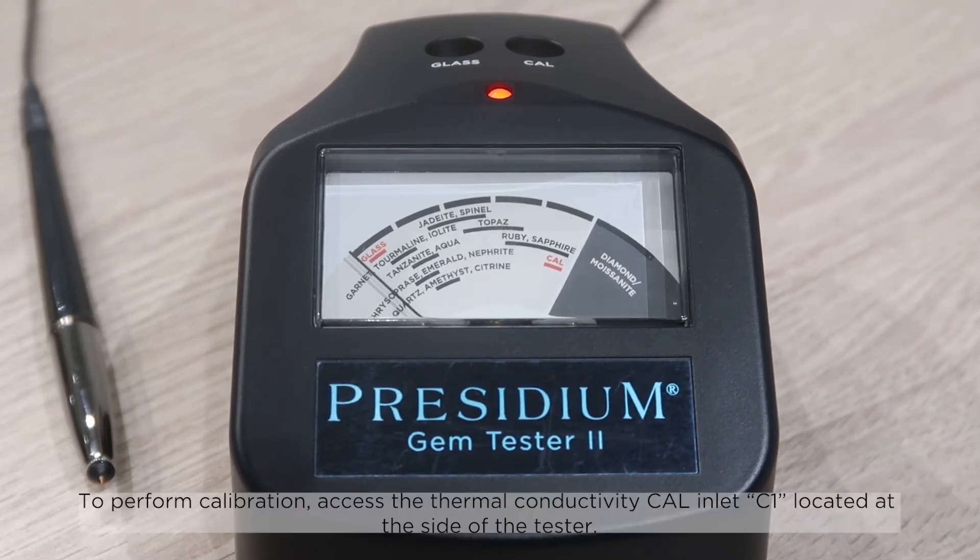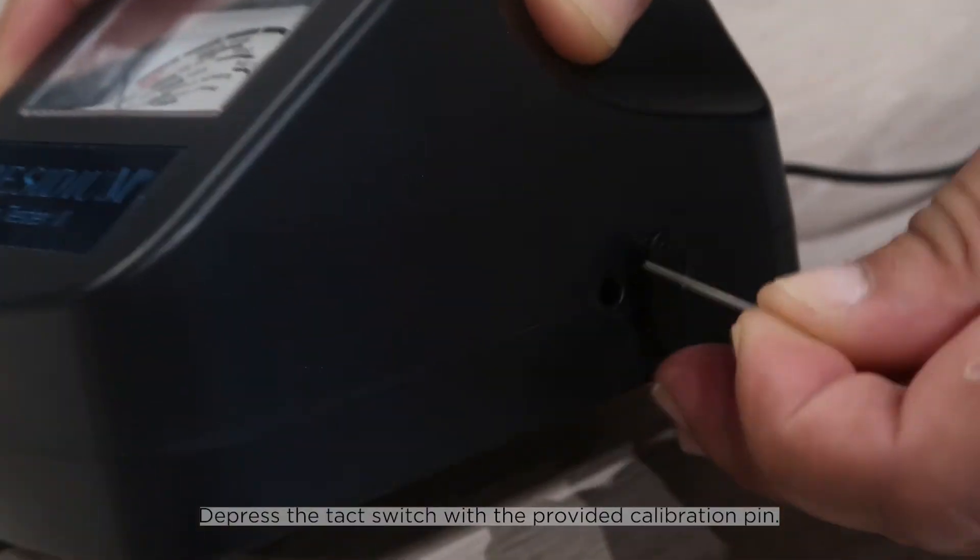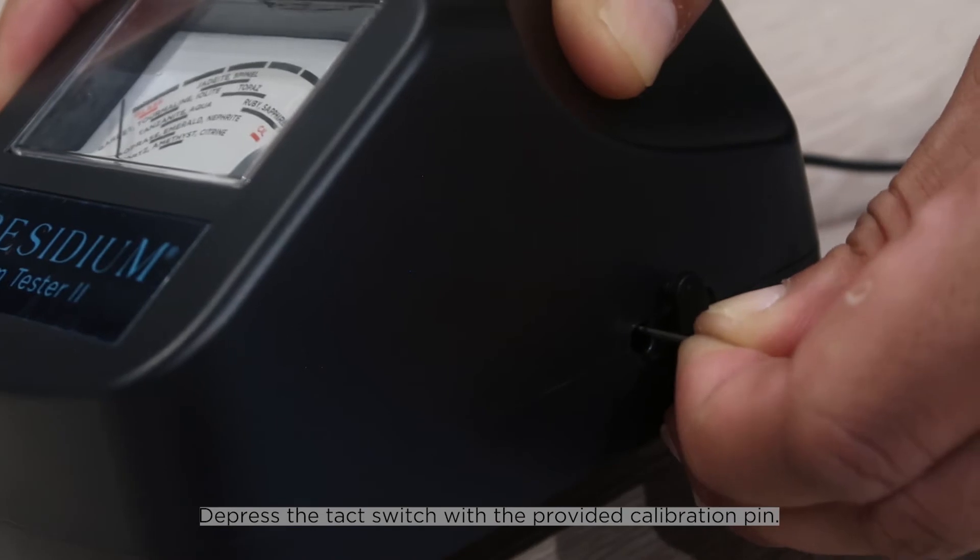To perform calibration, access the thermal conductivity cal inlet C1 located at the side of the tester. Depress the tact switch with the provided calibration pin.